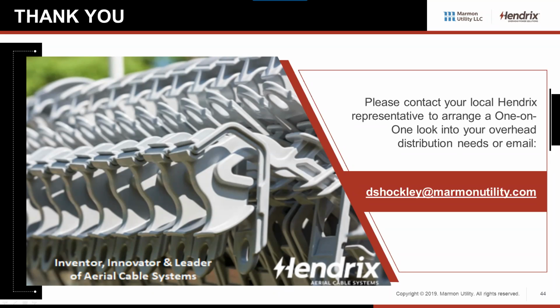I think in the past, we've recommended you cover up the taps. The problem is we've never really given you a good way to do it. And if you look at most of our standard drawings and some of our literature, we always show them as being exposed. I've got utilities that leave them open. I've got utilities that will tape them up or use some type of gel, cover or something over top of it. You're not hurting anything by covering up the taps.